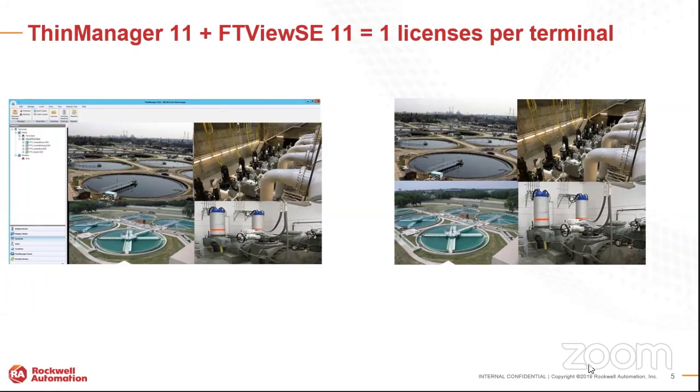And the screen to the right would be the other 4 that's sitting on a server, because you can have a redundant environment set up. So what you would look at is, let's say it's running on 2 different servers for a redundancy standpoint. You would need to have available 8 licenses because you're running 4 instances on this environment. But if this server goes down, you need 4 more available. That's on all other HMIs.